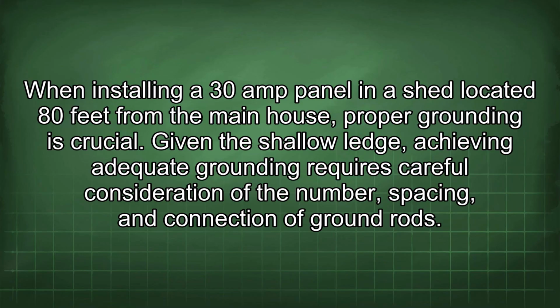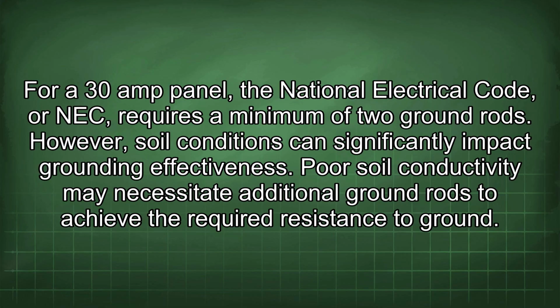When installing a 30 amp panel in a shed located 80 feet from the main house, proper grounding is crucial. Given the shallow ledge, achieving adequate grounding requires careful consideration of the number, spacing, and connection of ground rods. For a 30 amp panel, the National Electrical Code, or NEC, requires a minimum of 2 ground rods. However, soil conditions can significantly impact grounding effectiveness. Poor soil conductivity may necessitate additional ground rods to achieve the required resistance to ground.